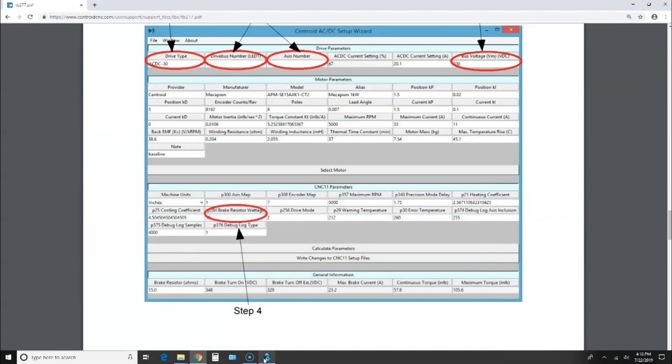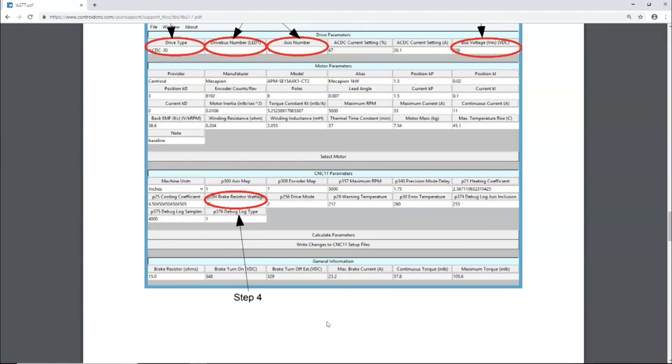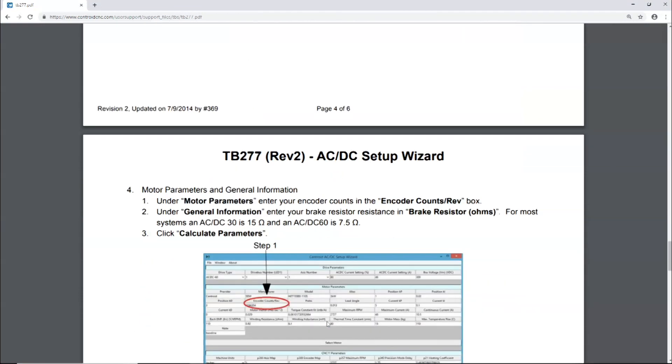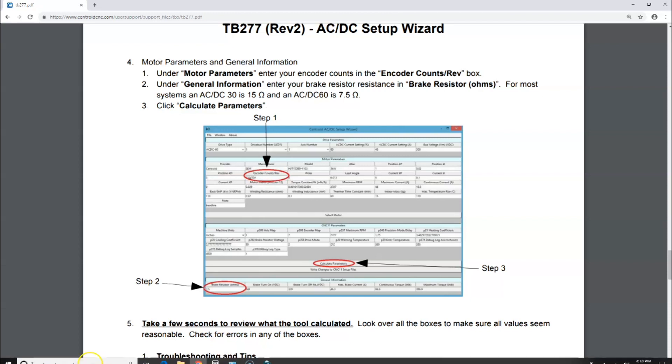Let's go back to the screen. Under motor parameters, enter your encoder counts in the encoder counts per rev box. Under general information, enter your brake resistor resistance in the brake resistor ohms. For most systems, AC/DC 30 is 15, and AC/DC 60 is seven and a half. Then click Calculate Parameters.